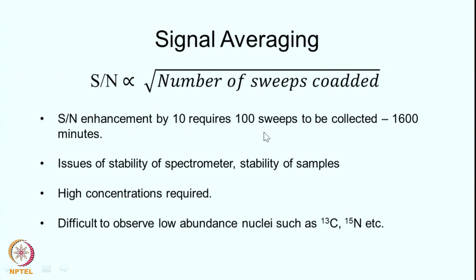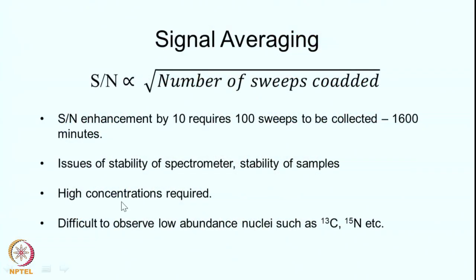This puts a lot of pressure on the spectrometer — the current and field must not vary, and samples must be stable for that long period. If signal-to-noise is very poor, one would need very high concentrations of sample, but high concentrations may require good solubility. It becomes especially difficult to observe low-abundance nuclei such as carbon-13 (1.1% natural abundance) and nitrogen-15 (0.37% natural abundance).